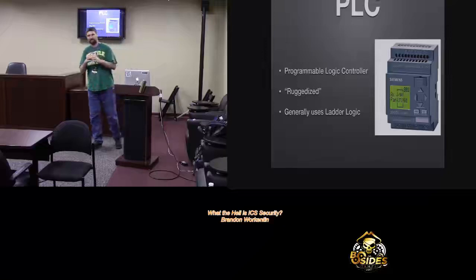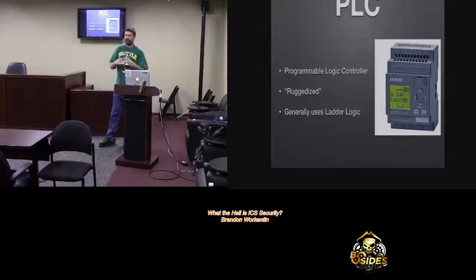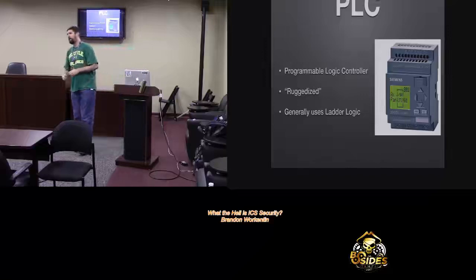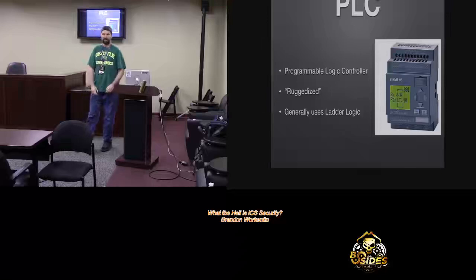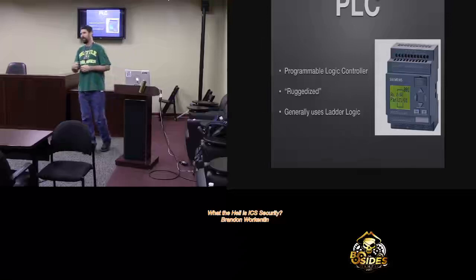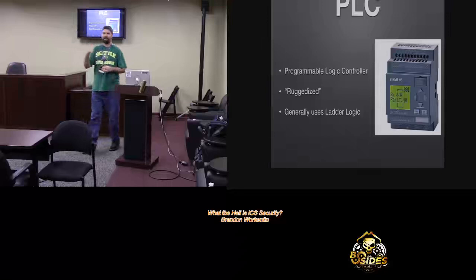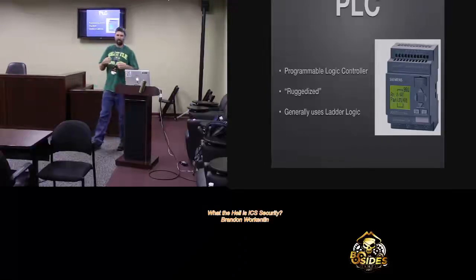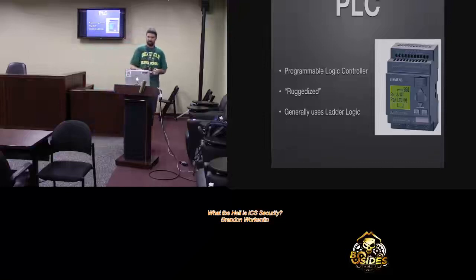These are small, ruggedized computers that usually use ladder logic. Ruggedized means they have to work in places like a cement factory with dust everywhere, or a substation in Minnesota where it gets down to negative 10 degrees. They have to withstand extremes in temperature and operating environment. Ladder logic is a simple, almost programming language, but really based off of Boolean logic.